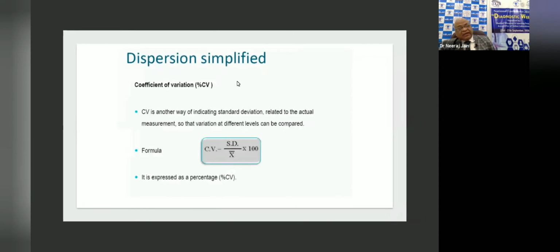Therefore, accreditation bodies also ask for CV%, because with this they can compare variation in different analytes, where the variation is more and where it is less. Always use this CV up to at least 1 decimal point. Because if you are calculating on your computer, it may give you 6.8236, 7.2498. That much is not required. And even 6%, 7%, 8% is not acceptable. Write 6.2, 6.4, and even if it is 6%, write 6.0. This is how we express it.